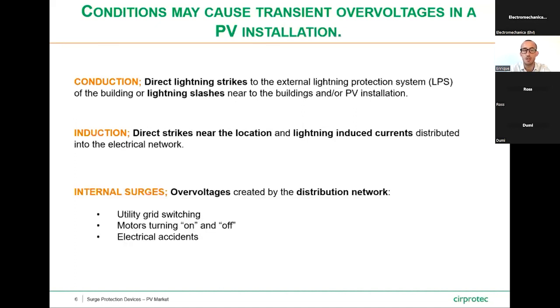And the last condition that may cause transient overvoltages in a PV installation is the internal surges. Those are overvoltages created by the distribution network, such as utility grid switching, motors turning on and turning off, or electrical accidents. Now, we'll check together the way the standards state to simulate the amount of energy depending on the origin of the surges.